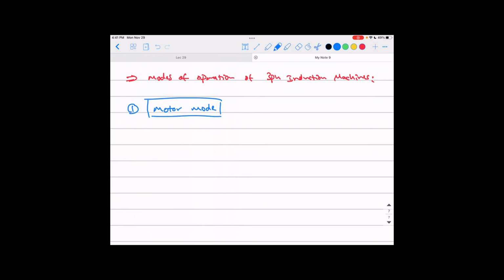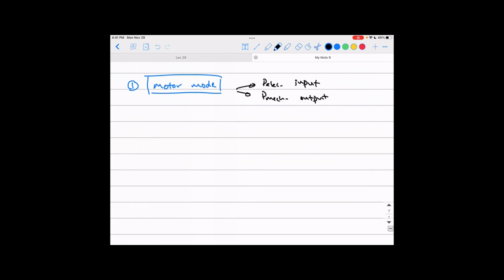How do we distinguish a motor mode? P electric is your input and P mechanical is your output. It's how any motor works: it takes electric power as input and converts it into mechanical power. Okay, guys? How does the machine work internally as a motor? If you remember, there is a stator, and this stator has a rotating magnetic field, like poles, and those are rotating around the circumference of the machine at the synchronous speed. Your rotor has the same set of poles, so you have south here and north here, coupled together like we said before, and rotating together at the same speed.